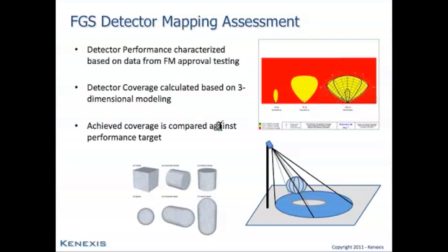Also, as you are performing analyses and looking at software tools that will generate cones of vision, it's important to ensure that the achieved coverage target is compared against the performance target that was provided or that was calculated based on the zone categorization to ensure that the performance targets are met. And this analysis needs to not only consider the footprint of the cone of vision of the optical fire detector at the elevation of interest, it also needs to consider the effects of shadows that are cast by objects that are in the path of the fire detector. So any obstruction between the fire detector and the elevation of interest will cast a shadow on the elevation of interest, which then needs to be essentially removed from the coverage map.